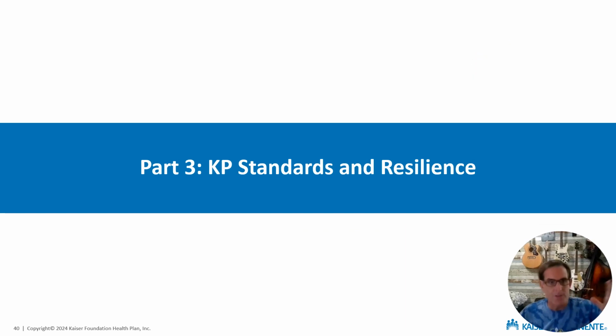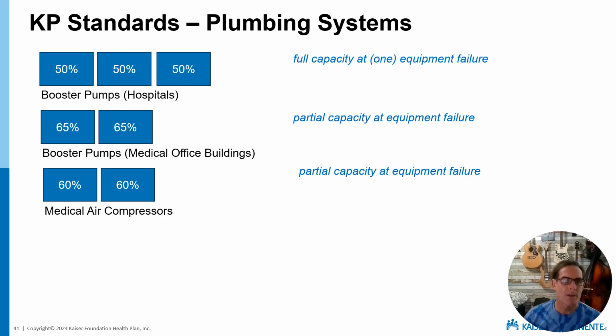So ostensibly, this is the main event here. The next 6 slides will show what the KP standard requirements are for resiliency and redundancy within our standards. And we'll start with plumbing. Our standards mostly call for partial capacity at one equipment failure. We do have a 3-pump system called out for our booster pumps at hospitals. And by the way, if it's not shown here in the slides, then our standard is a single duty. So for ejector pumps, water heaters, etc., single duty is fine.